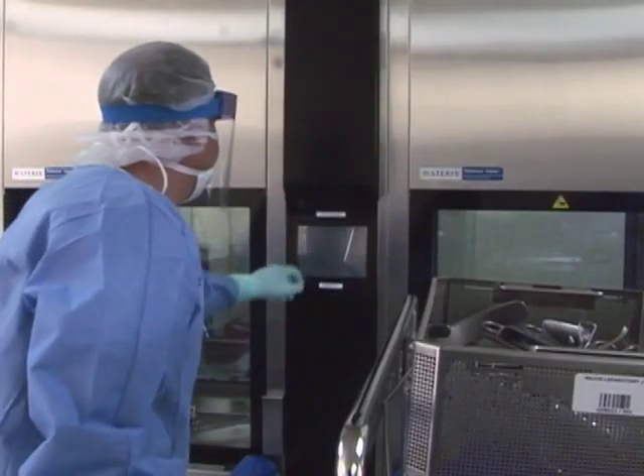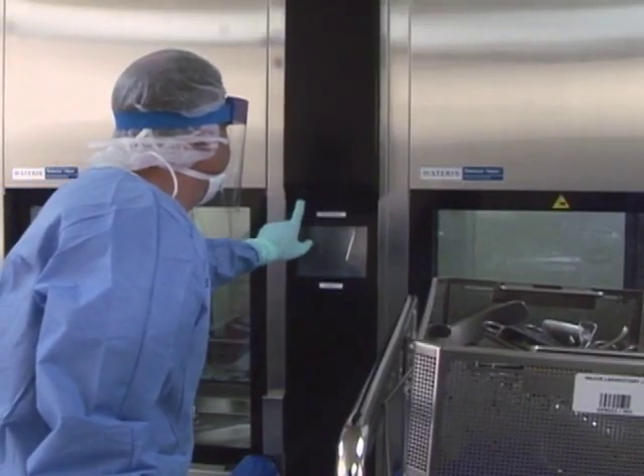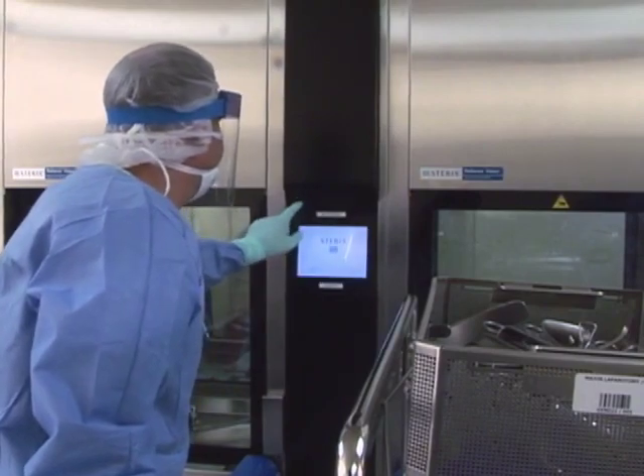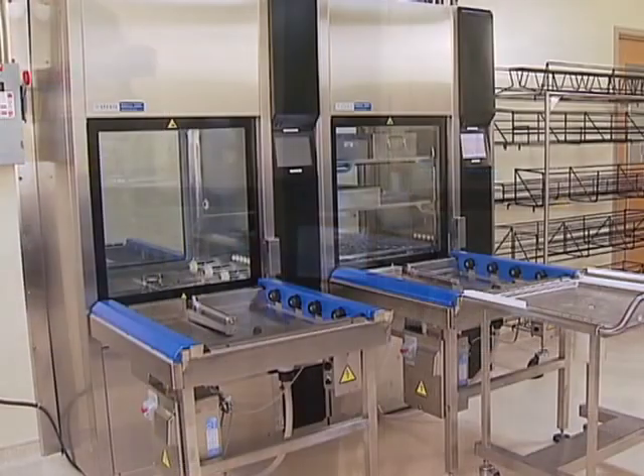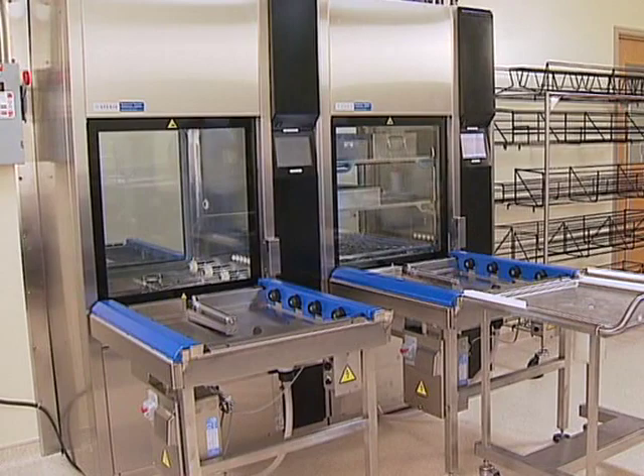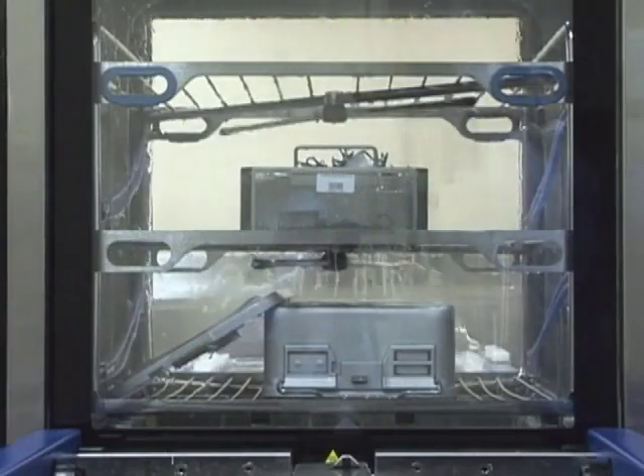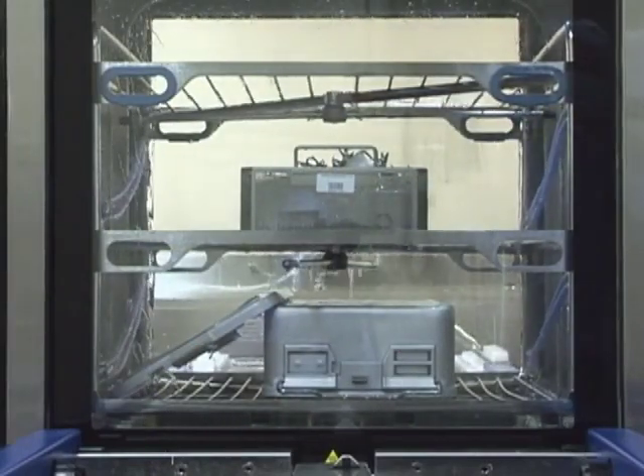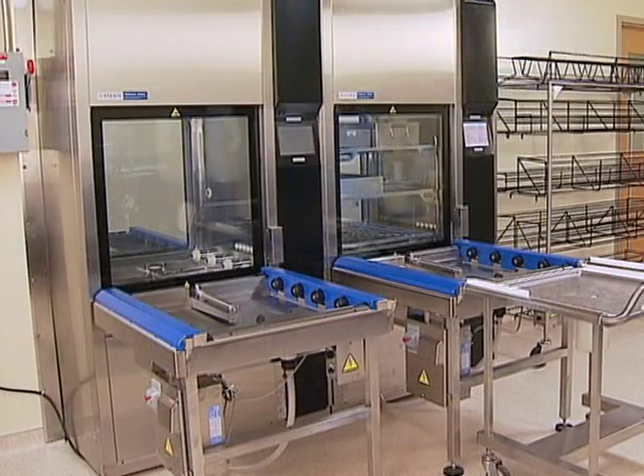The power switch is a rocker switch located above both the load and unload side touch screens. Never power down the washer in mid-cycle mode. This main power switch is also used as an emergency stop switch. The power must remain off for 8 minutes in order to completely shut down the PC control.